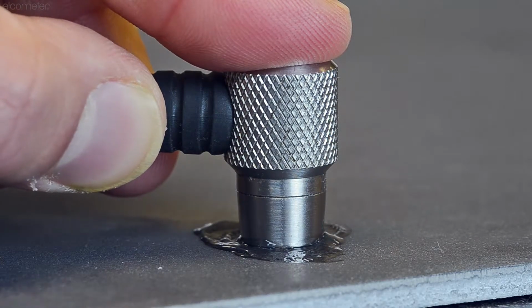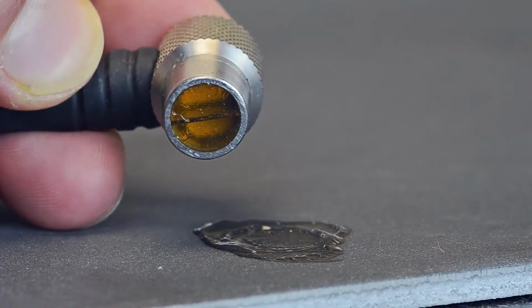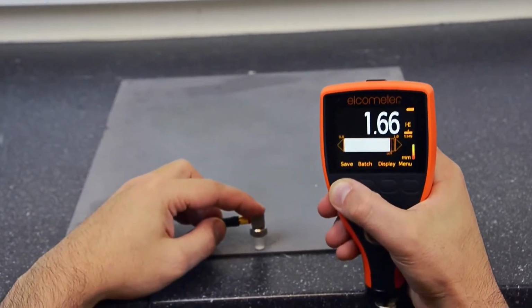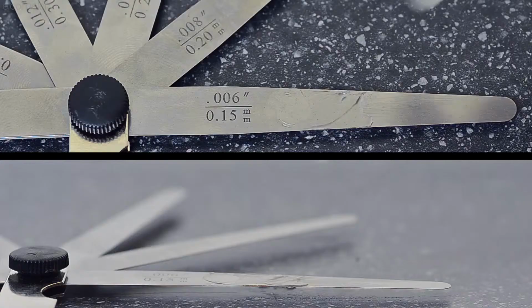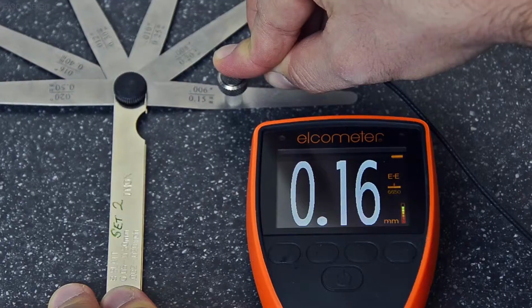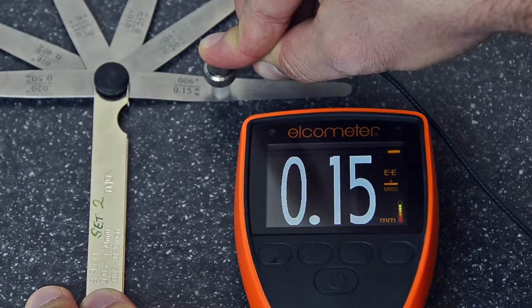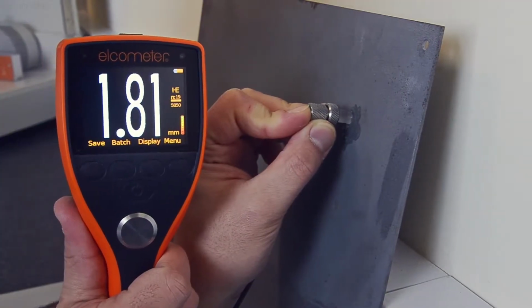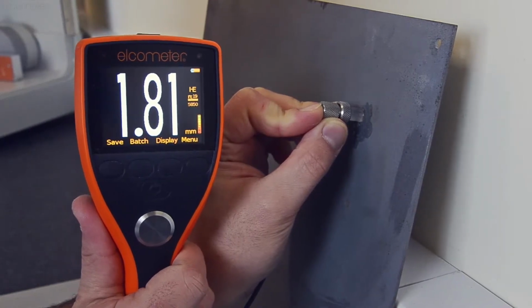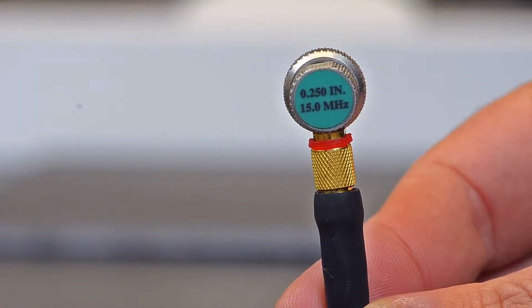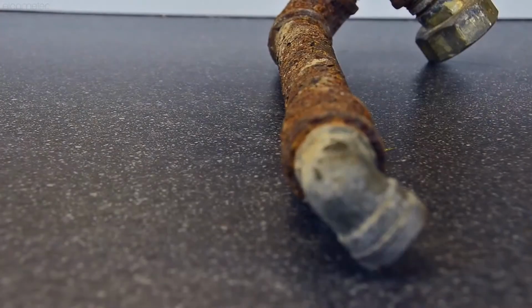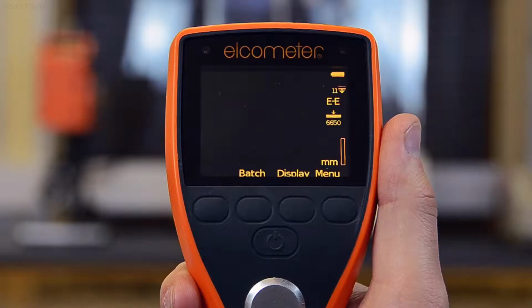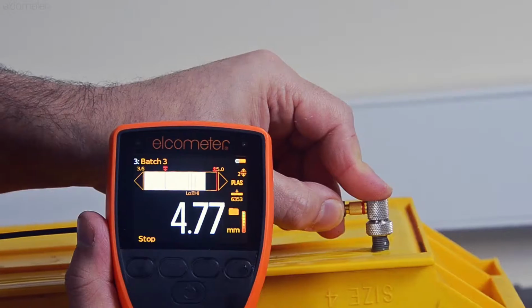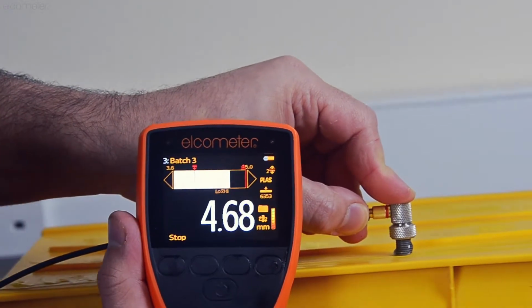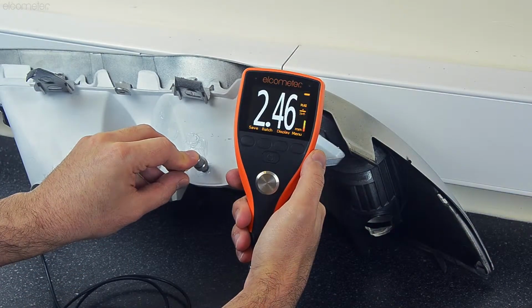Unlike the Elcometer 304, which uses dual element transducers, the Elcometer 307 precision thickness gauge uses single element transducers and provides precise, accurate material thicknesses to 1/100th of a millimetre or 1,000th of an inch. Ideal for measuring the thickness of thin, uncoated materials such as steel, titanium, and plastic with pinpoint accuracy. Using a single element transducer and a suitable delay line, it will effortlessly measure thin materials from 0.15 mm. In the gauge's plastic mode, you can even measure thin plastics up to 5 mm.